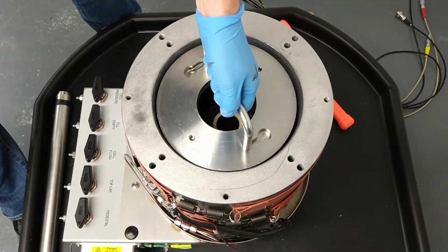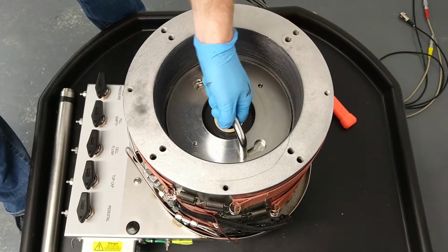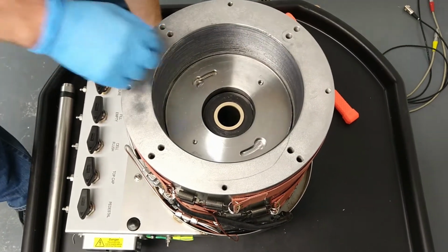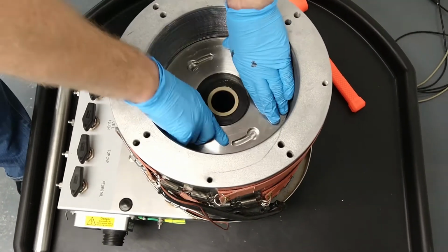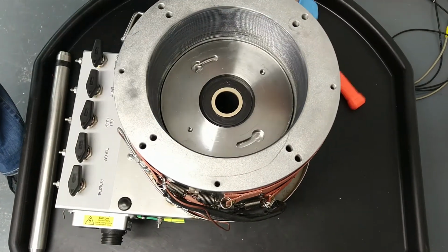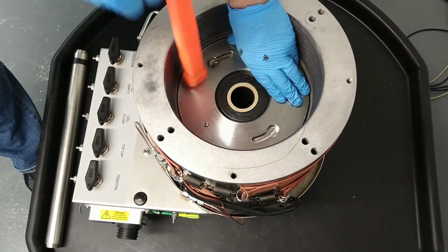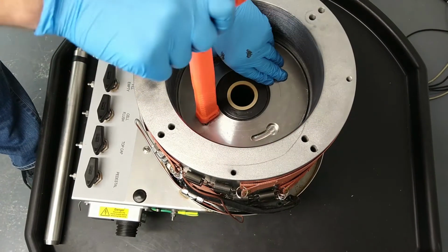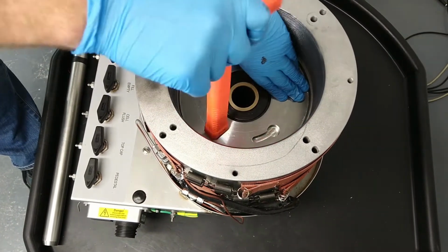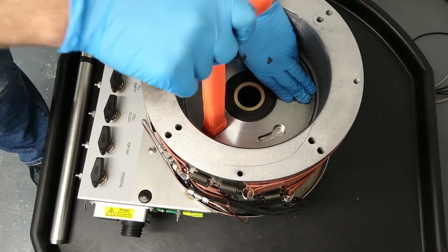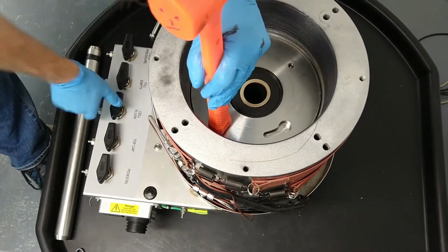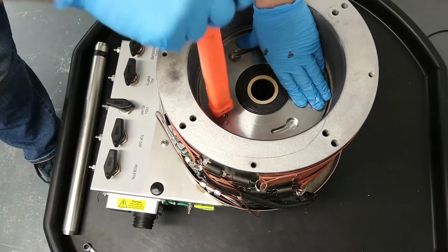Place the sealing ring inside the cell wall using the handle provided. Once loosely in place, gently tap the sealing ring into place, working around in a circular motion to ensure the sealing plate lowers evenly into place. The cell flush valve should be opened to allow the air to escape and allow the sealing plate to locate correctly.